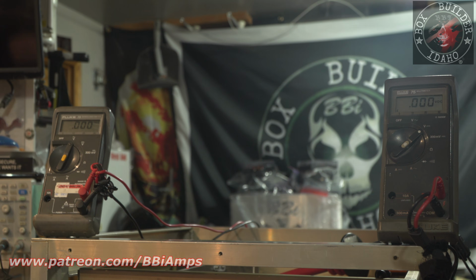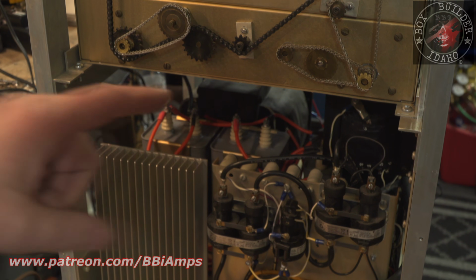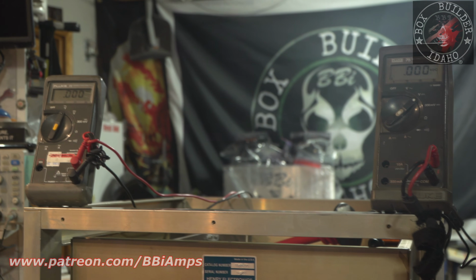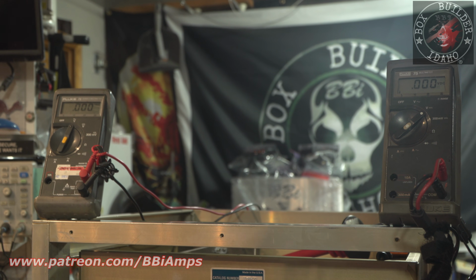Yes, sir. Here's a question I've always had. So I had the tap set on the 250 volt tap for our first test, our lowest voltage that we can achieve on our secondary, or on the primary side from the secondary. So the primary side I had set at the 250 volt tap, so it runs great at 240. I've always been interested to see what would happen if we go to 230. The primary limiting factor is the oil filled capacitors, which are 8,000 volts each, and they're only 6 microfarads a piece, but it's okay, they're in series, so it's okay, right?